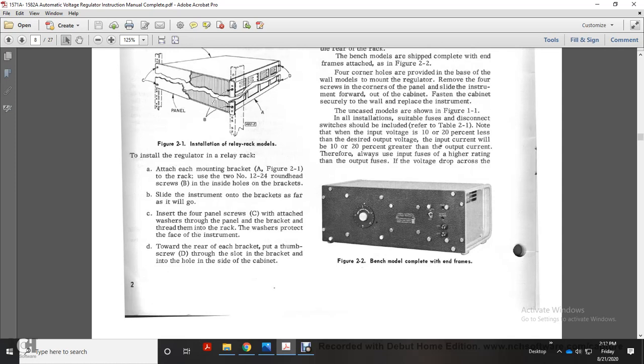Slide the instrument into the brackets as far as it will go. Insert the four panel screws, each with a washer, through the panel and bracket and thread them into the rack. The washers protect the face of the instrument. Toward the rear of each bracket, put a thumbscrew D through the slot in the bracket and into the holes in the side of the cabinet.